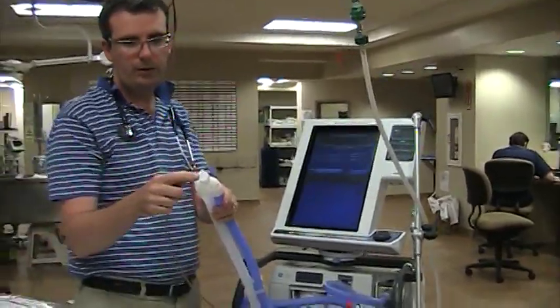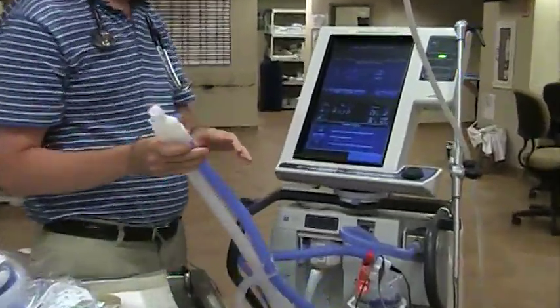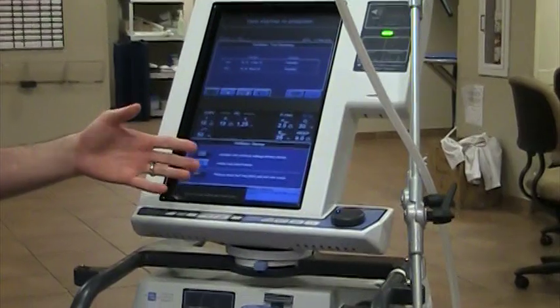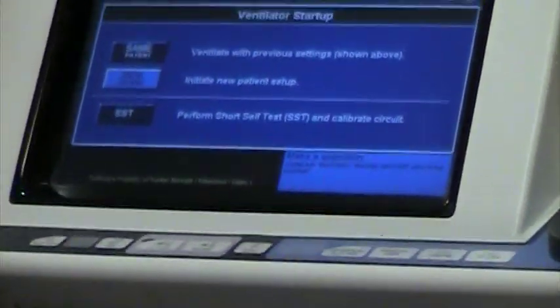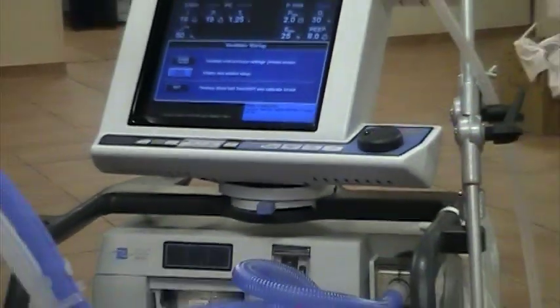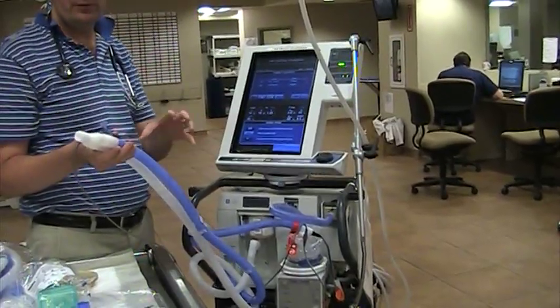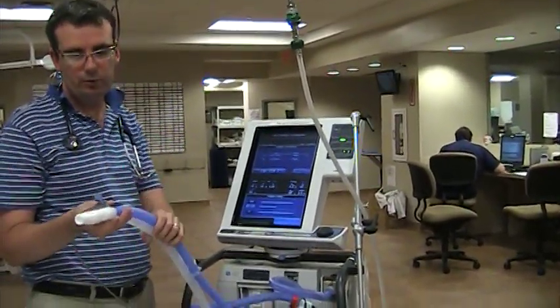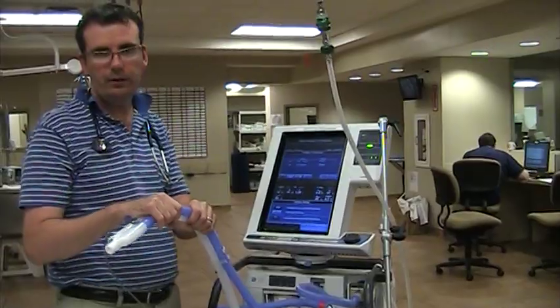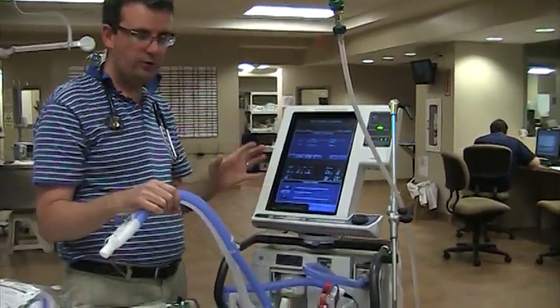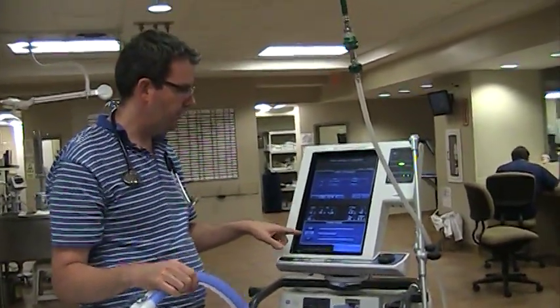And again, remember that we have the cap off. So what we're going to do is a short self-test, which basically calibrates the machine to this particular tubing. It doesn't have to occur if you know that the patient on the ventilator prior to this was on the same size tubing. But just for the purpose of this demonstration, we'll do the short self-test.